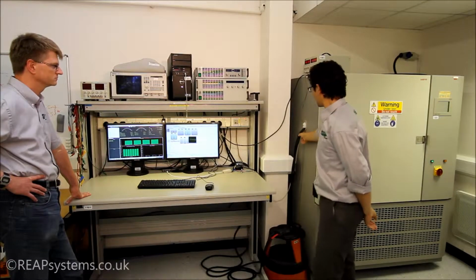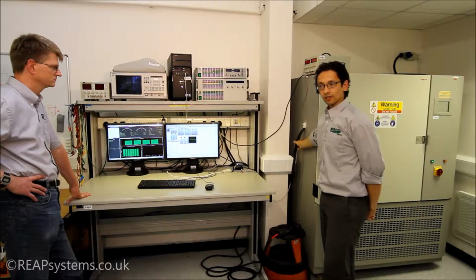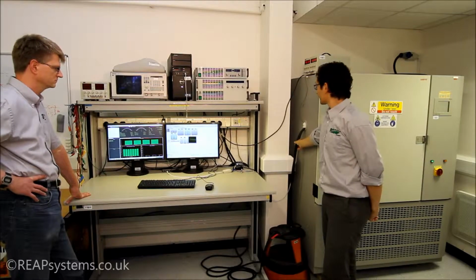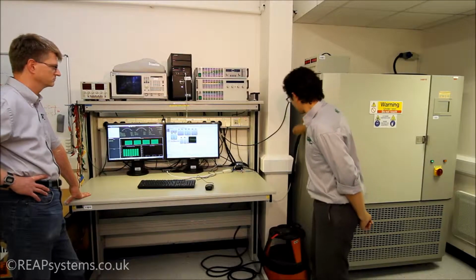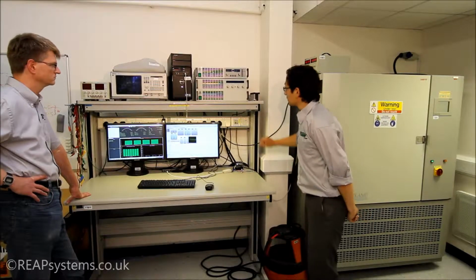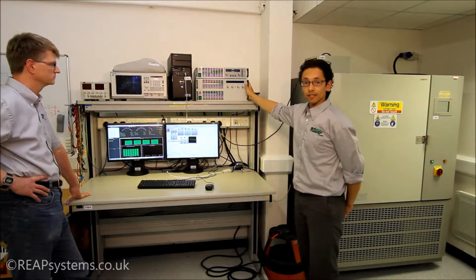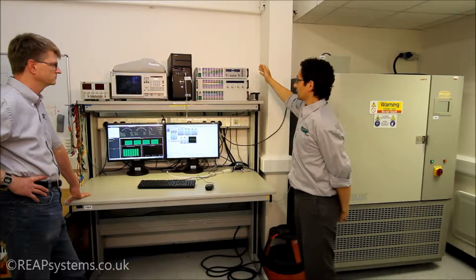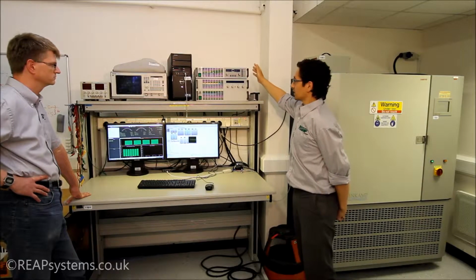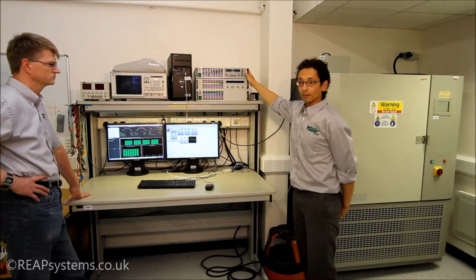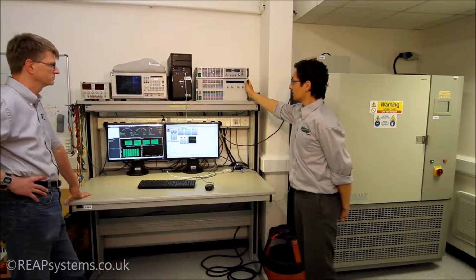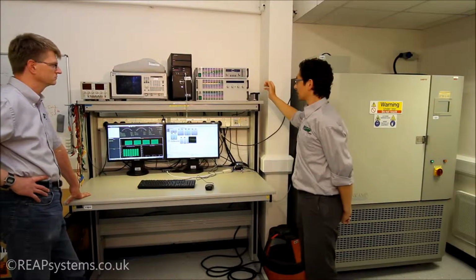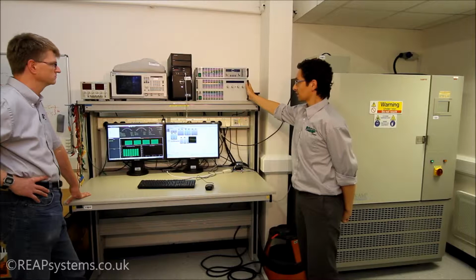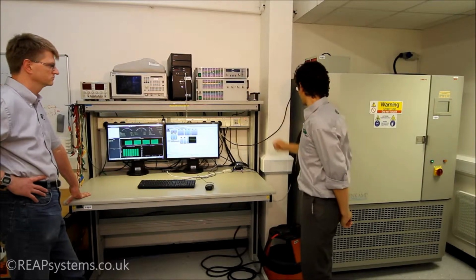Through the porthole we have the high power cable which allows us to charge and discharge the battery. This is connected via this big cable here to our electronic load and our power supply. This equipment allows us to charge the battery up to 120 amps or discharge it up to 400 amps. Today we'll be discharging the load at 300 amps.